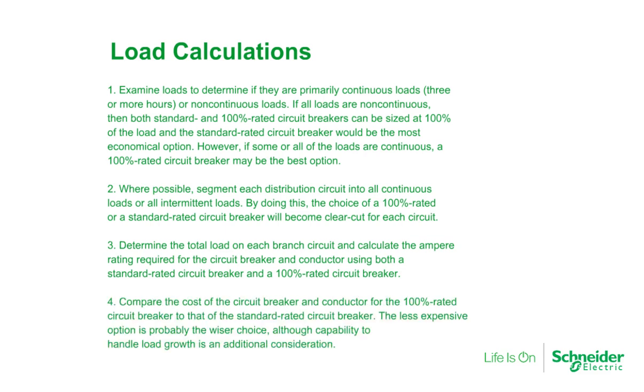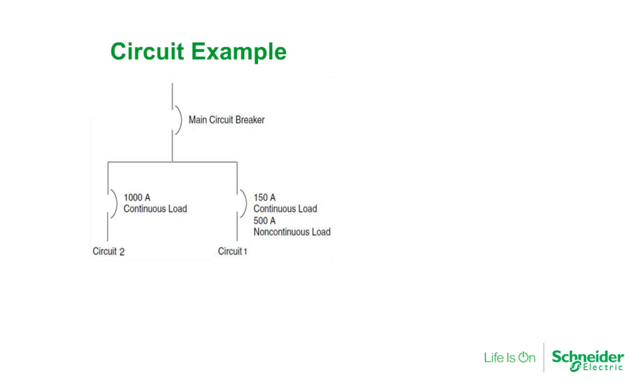Compare the cost of the circuit breaker and conductor for the 100% rated circuit breaker to that of the standard rated circuit breaker. The less expensive option is probably the wiser choice, although capability to handle load growth is an additional concern.